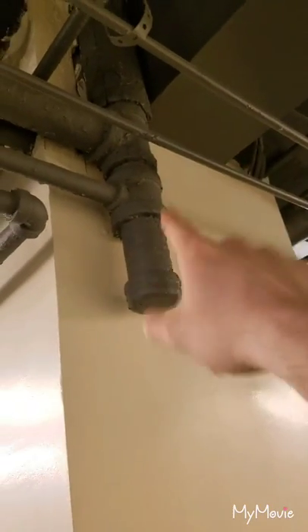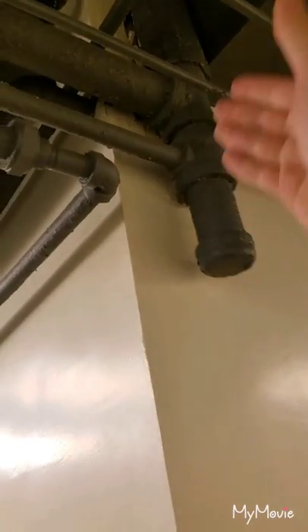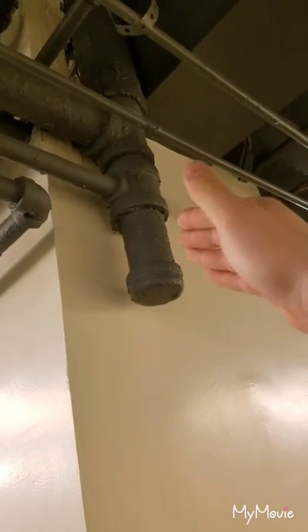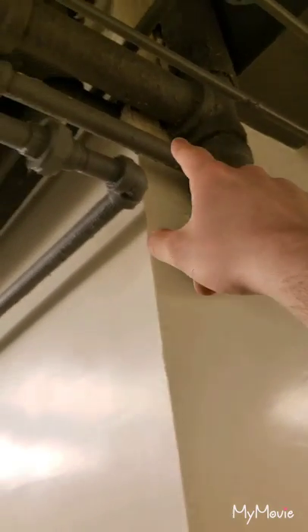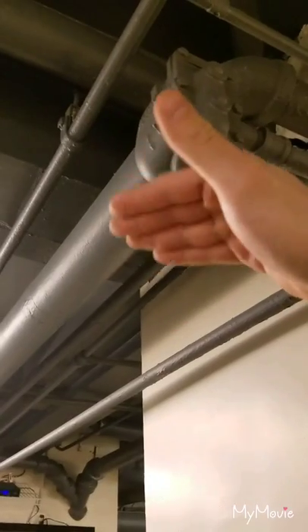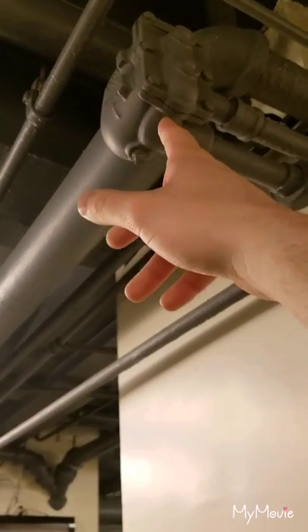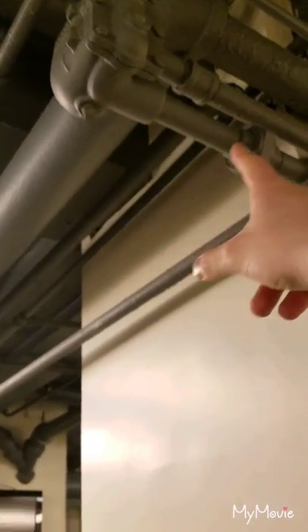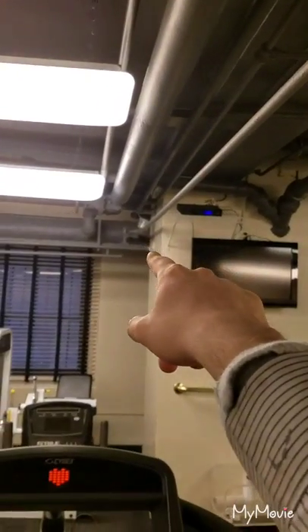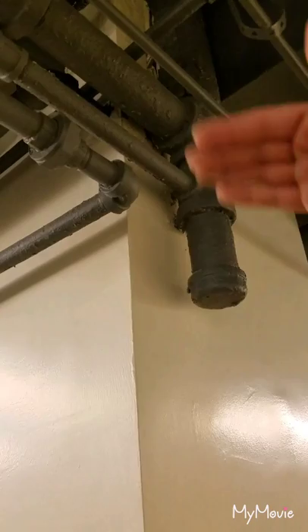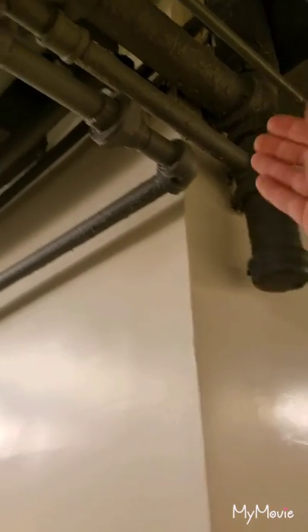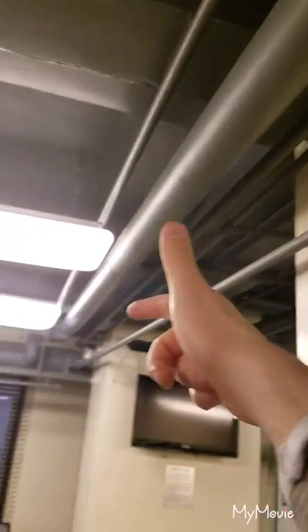Okay, this is the main steam riser going up to this line of apartments. And off the bottom, now not all of them in the building have this, but it does have a drip off here in the bottom with a ball lift or ball swing steam trap. Comes over and goes back into the condensate return. So the water that accumulates from that steam going up settles here in the bottom and will come into the trap and out.